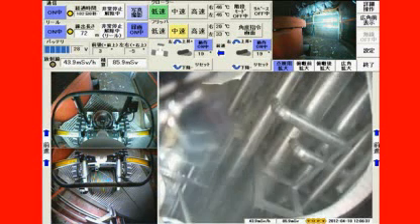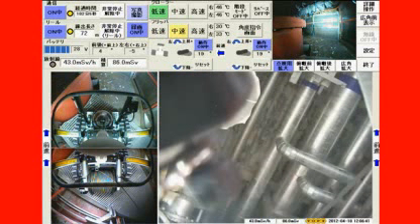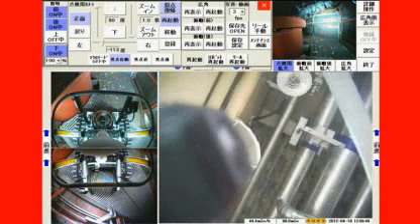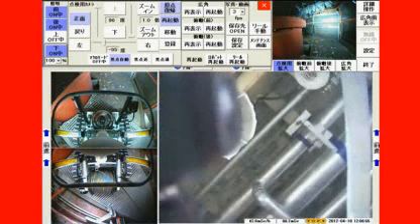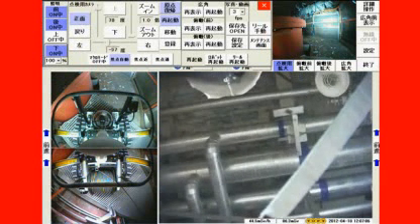Under normal circumstances, a cold shutdown can be reached when reactors are halted safely and the water inside drops below 100 degrees. But since the Fukushima plant has suffered nuclear fuel meltdowns, the criteria are somewhat different. That's why a cold shutdown has been redefined as bringing the temperatures at the bottom of the crippled reactors to below 100 degrees. Another requirement is curbing the release of radioactive substances so that additional human exposure near the plant can be limited to 1 millisievert per year or less.